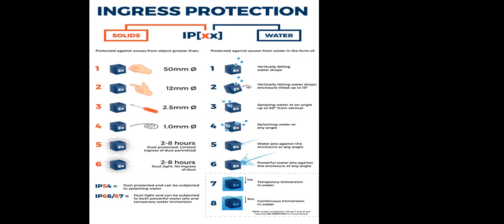Now, if I say 54, that is dust protected, limited ingress of dust permitted, 2 to 8 hours, and 4 stands for splashing water at any angle. Why is it so important in our selection of any electrical equipment? Because of its application. When we decide where to install a particular panel, distribution board or socket, we need to ensure the protection of that equipment.